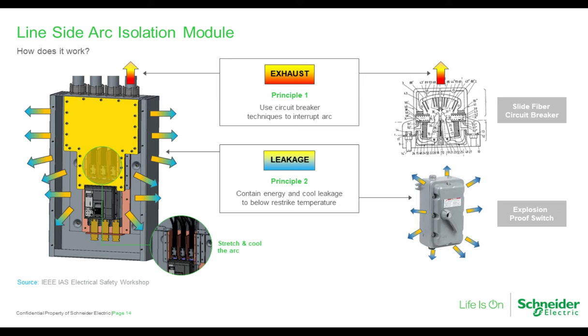As it turns out, we can reliably clear an arc like a circuit breaker, but it takes us a few milliseconds to do so. This is because, like a circuit breaker, the design is intended to starve the arc of heat so that it dies of cold as it approaches our forced current 0. During the arc period, we control where the arc can go, ensure that its length and therefore its arcing voltage is maintained, and we cool it by adding generous amounts of ablatives. We evacuate the excess energy out the top in the exhaust. So basically we emulate what a circuit breaker does, but with no moving parts.